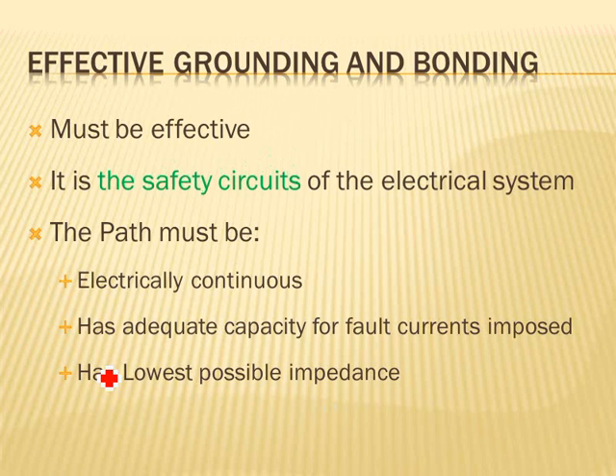I can't think of anybody who would have that, even when you drop a wrench inside the switchgear, you typically get either phase to phase or phase to neutral. Phase to phase to phase, which is the worst scenario, is, I would say, less than 5% of the time that you encounter it. And we size the equipment to handle that 5% of the time. So your chances of having a phase-to-phase-to-phase short circuit in the building is probably 100 times less than your chances of being hit by drunk drivers driving in Minnesota around the holidays. But we still size for it though.